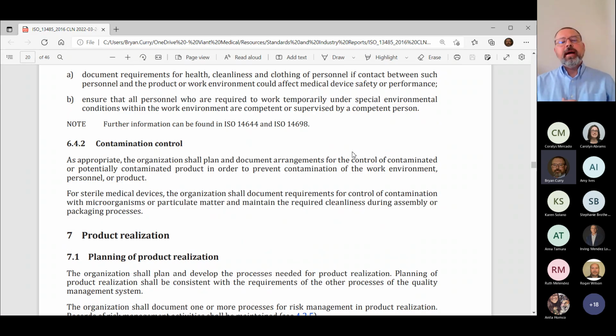So we have this environmental monitoring program, and we also certify our clean rooms. When we certify our clean rooms, they do some of the same testing that we do during routine environmental monitoring - the air and surface viable sampling. They'll also do the particulate sampling, but they are also looking at things like the number of air changes in the clean room per hour.